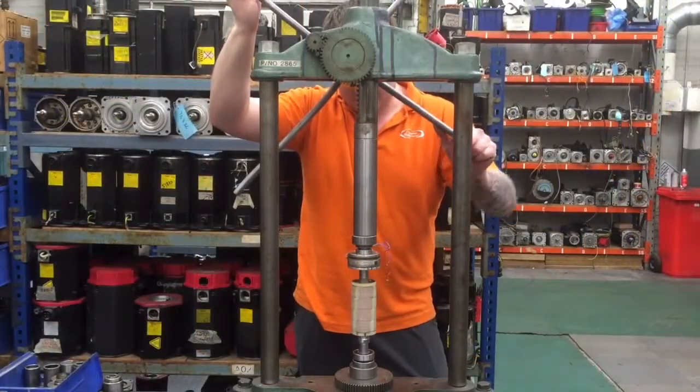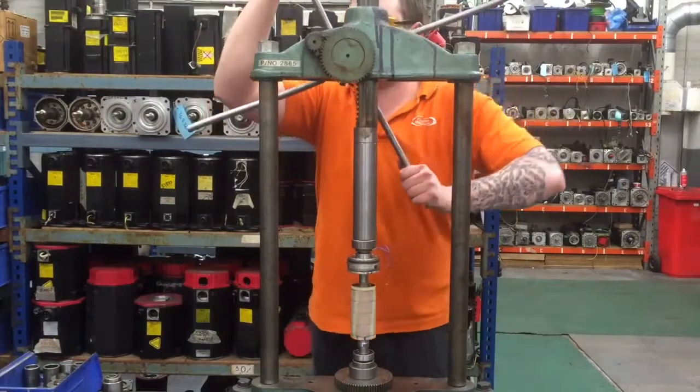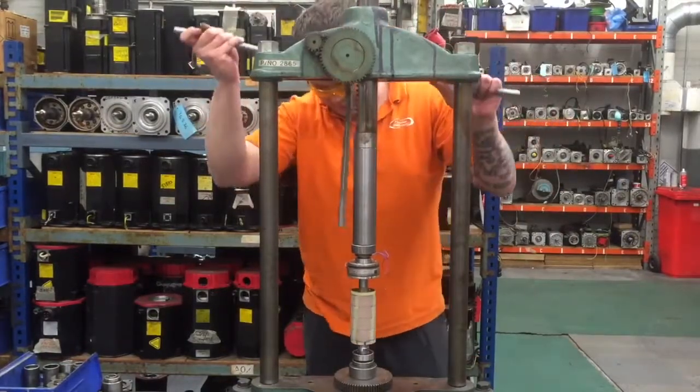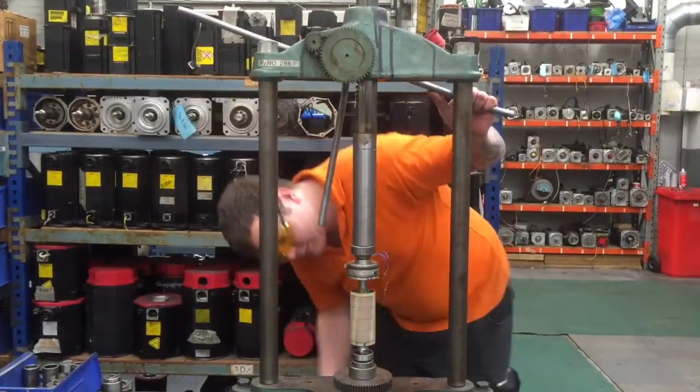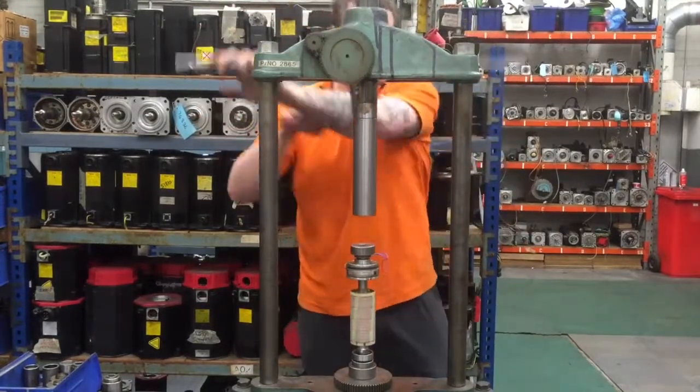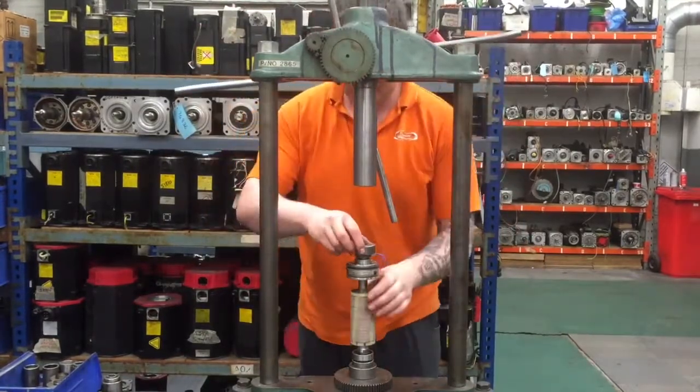We will fit the drive end bearing now again using the same cold pressing method with the fitments on the inner race of the bearing to press down against the shoulder. Once we are happy with this, we will then remove the rotor and we will build the motor up ready for testing.